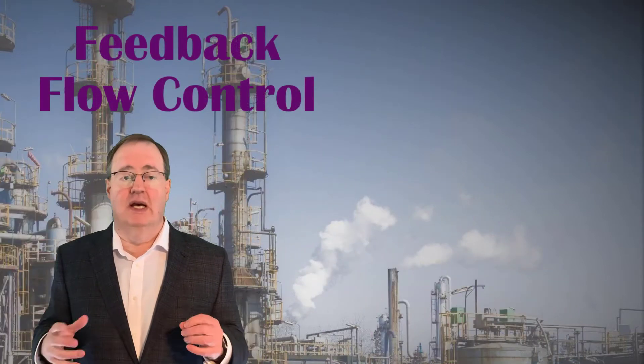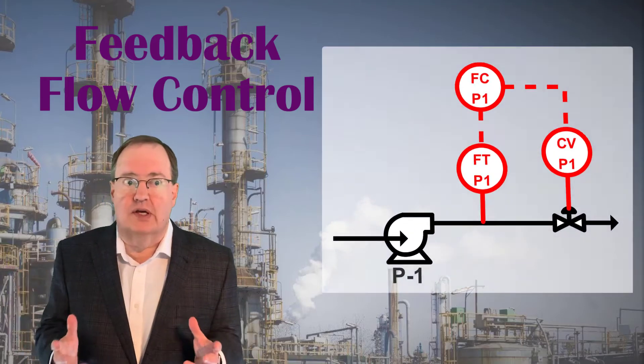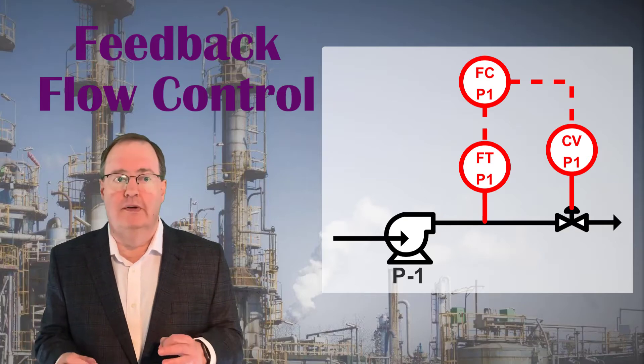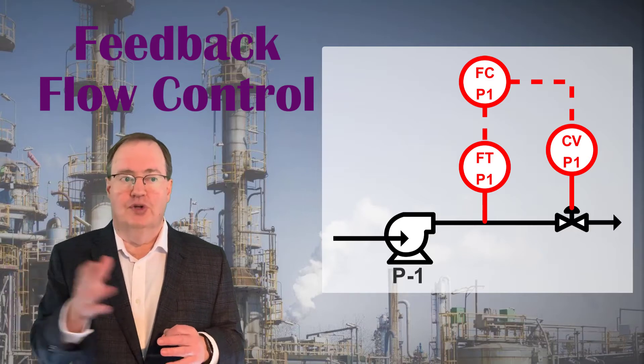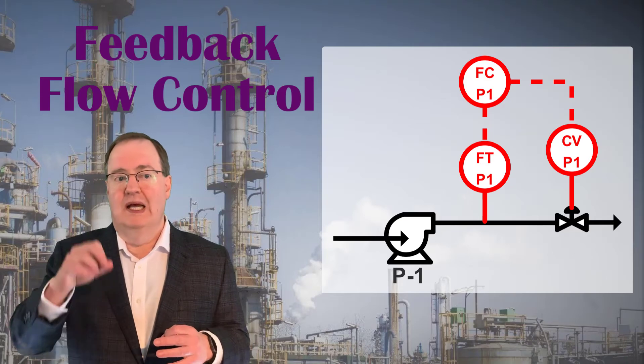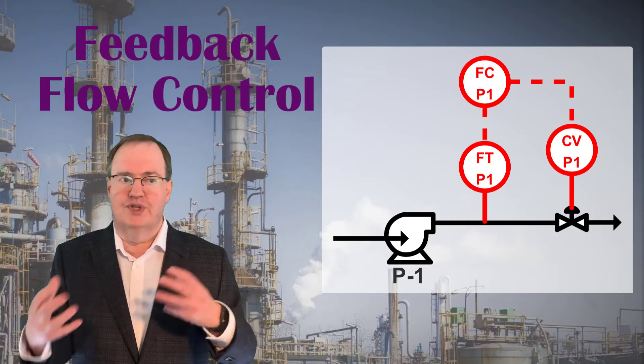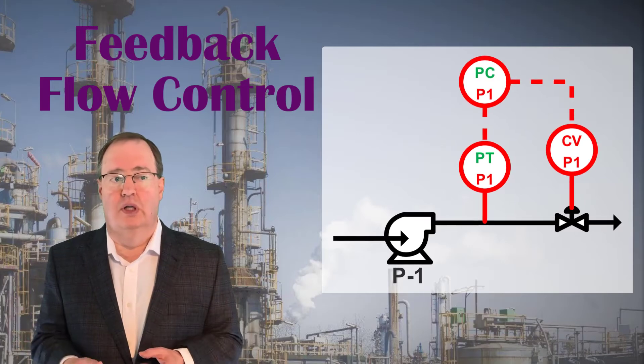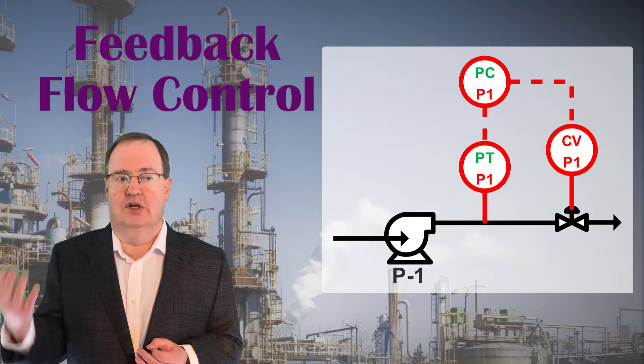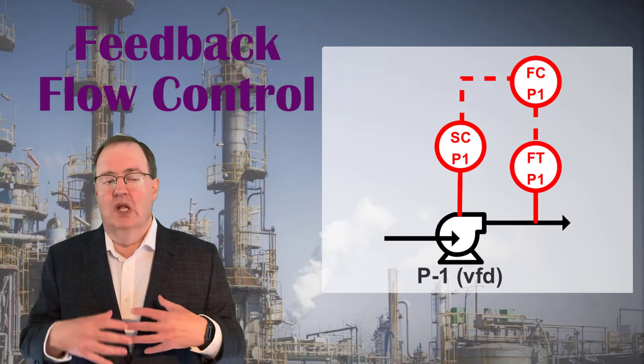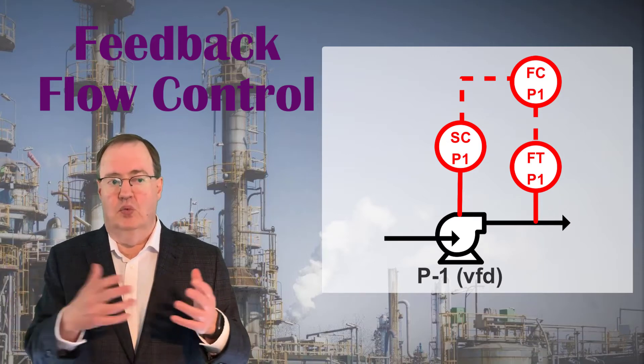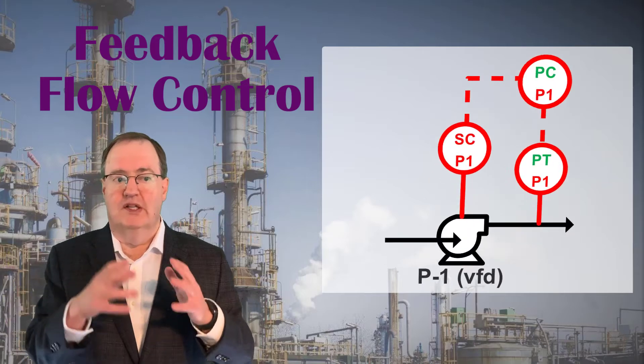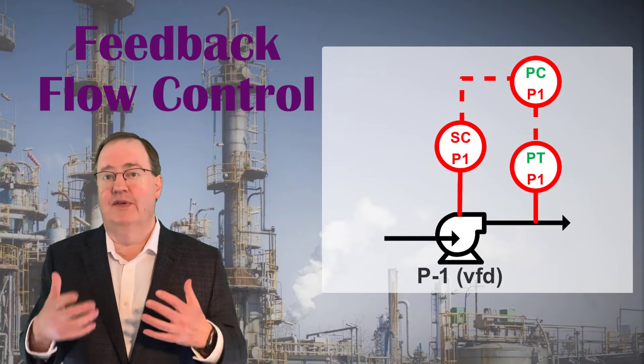When we draw a piping and instrumentation diagram for a simple feedback controller for flow or pressure, it looks like this. Here we have a single-speed pump, P1, adding a constant energy, with a control valve, CVP1, subtracting energy to control flow. A flow transmitter, FTP1, measures the flow, and FCP1 is a feedback controller that opens and closes CVP1 to achieve a target flow rate. The diagram would be identical for pressure control, except the F's would become P's for the sensor and controller. In the alternate approach, P1 is a variable-speed pump, indicated with the SCP1 tag for its speed controller. We can control the flow or the pressure by controlling the speed of P1 and therefore the energy added, without having a control valve.